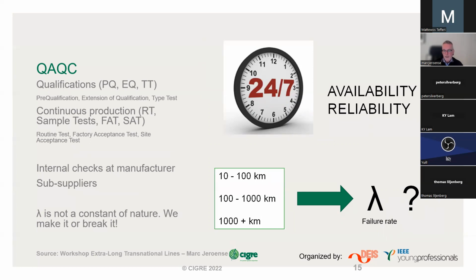TSOs, and in the end you and me, still want the highest availability and reliability. That means the failure rate per kilometer that we could accept must go down. If I double the length of the transmission line, I would suddenly require half the failure rate to have the same availability in the end.